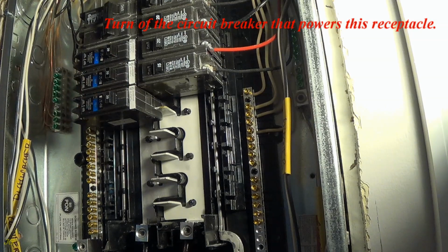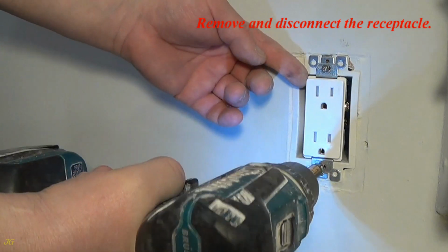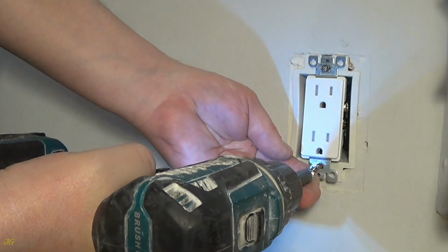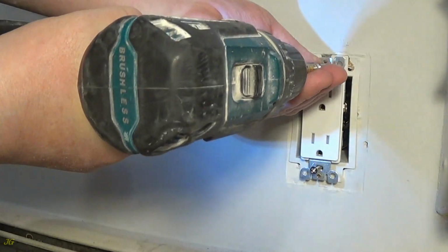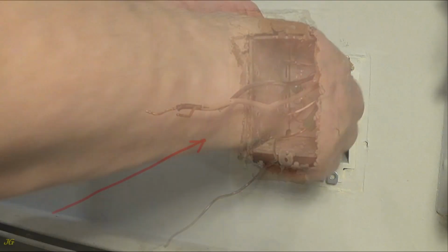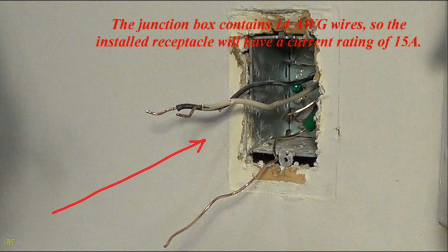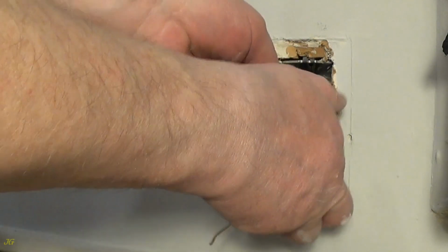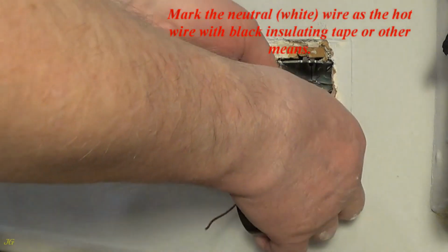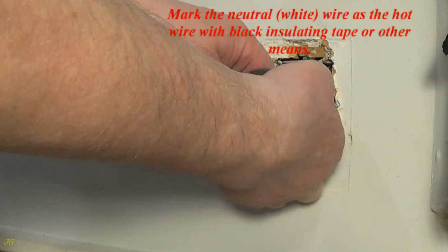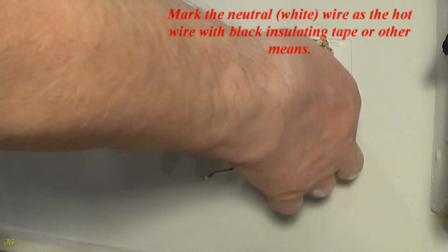Turn off the circuit breaker that powers this receptacle. Remove and disconnect the receptacle. The junction box contains 14-gauge wires, so the installed receptacle will have a current rating of 15 amps. Mark the neutral, white, wire as the hot wire with black insulating tape or other means.